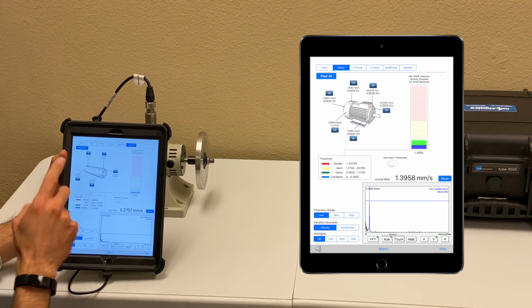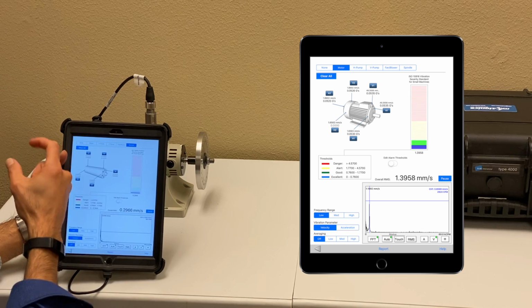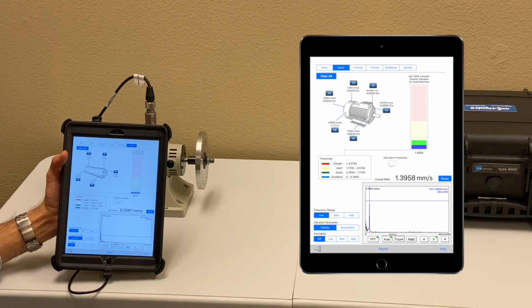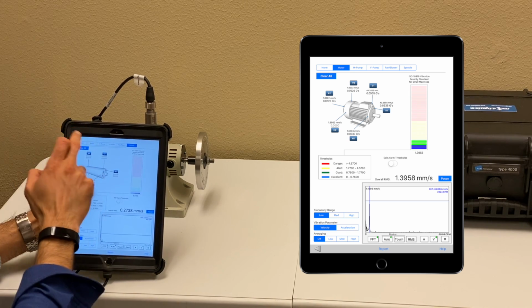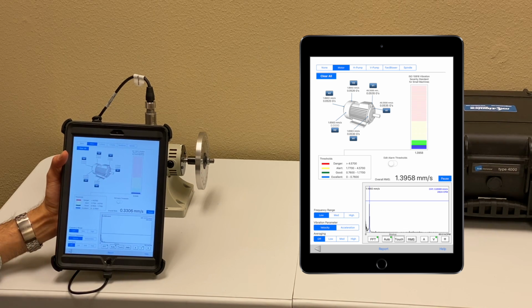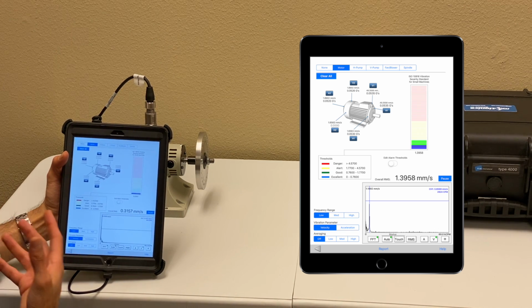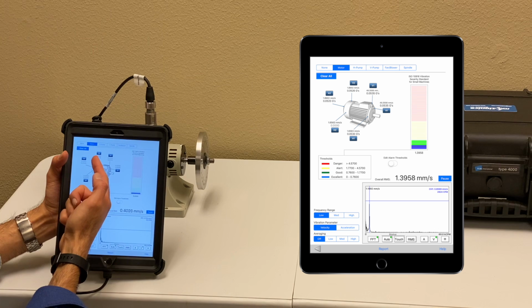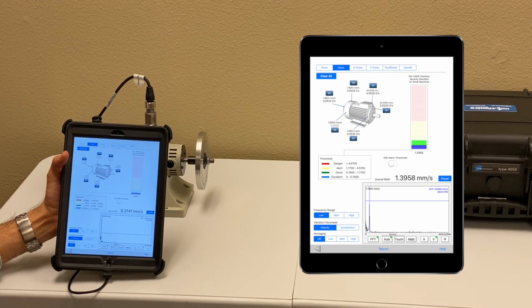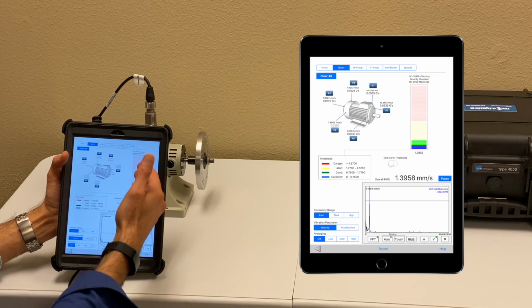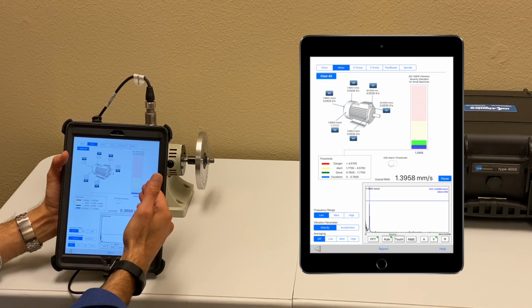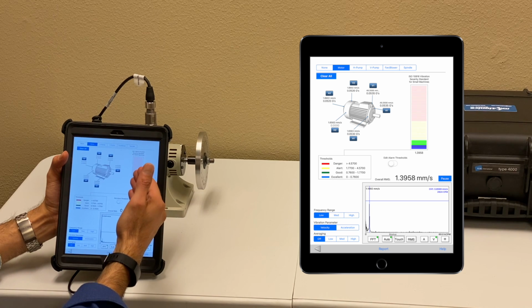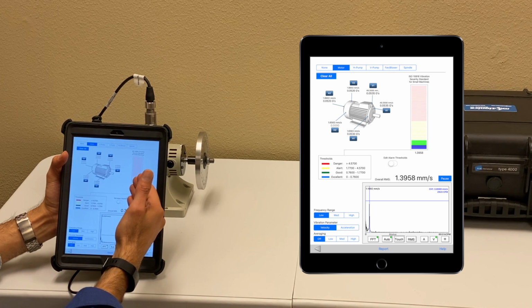Basically you just tap that point, and it's going to capture that vibration and save it for that spot. Let's say in our case it's a motor. For the motor, you have 6 predefined spots: front, back, horizontal, vertical, and axial. So you have 6 measurements, and for each point you're going to capture vibration, acceleration, and velocity, all in one shot. You're also going to record the overall vibration as a meter based on the ISO standard here.